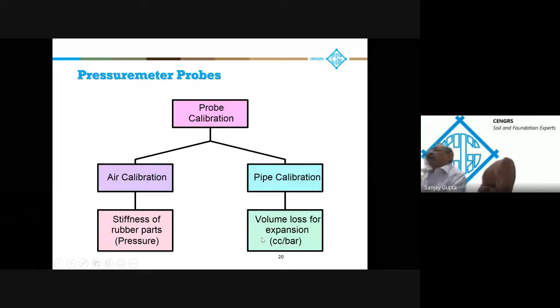Now, as you have understood, your probes and the coaxial cable are all flexible materials, right? Probes are made of rubber, so they will have their own stiffness, expansion properties, or pressure losses. So we do need calibration of the probe. Now there are two types of calibrations required. One is the calibration which correlates with the stiffness of the rubber part, that means the pressure: how much pressure one loses when you are expanding the probe. Similarly, you have another one known as pipe calibration. It is for the volume loss, for the expansion in the coaxial cable, etc. Whenever you are putting the pressure, there will be some volume loss. So remember, these are the two corrections, the air calibration and the pipe calibration, which we need to have on site prior to conducting the test.